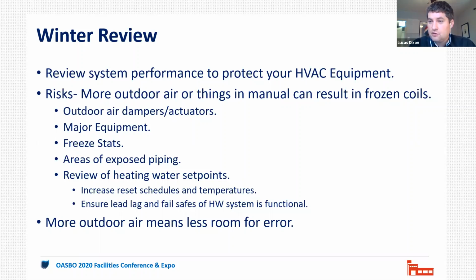If you've had your damper open for several months, make sure that it hasn't come loose. Your linkages are well lubricated and you're able to close that damper as the unit works to protect itself. I mean, the bottom line is although modulating down outside air to protect from a freezestat trip will reduce outside airflow, a tripped unit delivers no outside air. So it's better to make sure this stuff works before it becomes an issue where it's not running at all. The last thing anybody wants to do is to be cleaning up after a frozen coil. Amen.